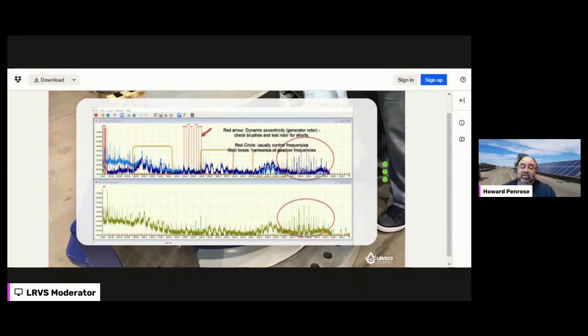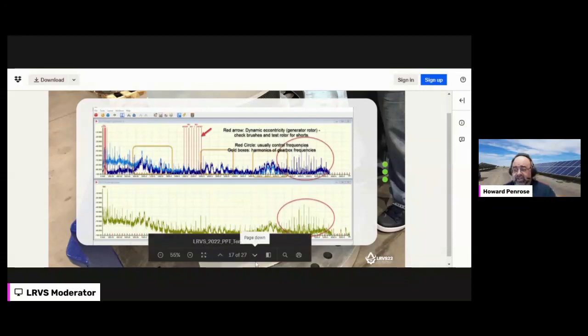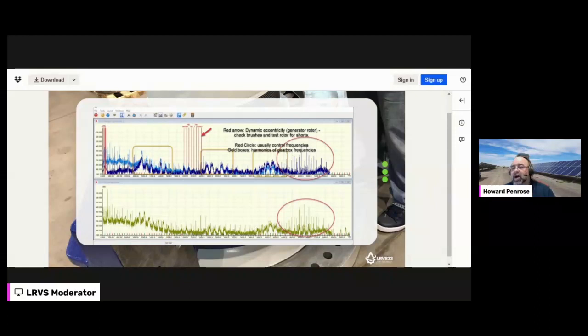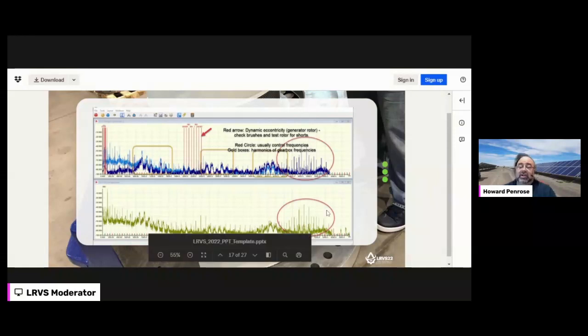Firing frequencies of the drives, which is the circled part on the right, is actually the second harmonic. And then eccentricity related issues, which all drive towards the different problems associated with the machine. In this case, they thought they were tripping because of the generator. It actually turned out to be all of the problems, gear meshing and binding, going on in the gearbox, and they weren't able to run it long enough to analyze it with other technology. And they didn't see the problems with the boroscope.